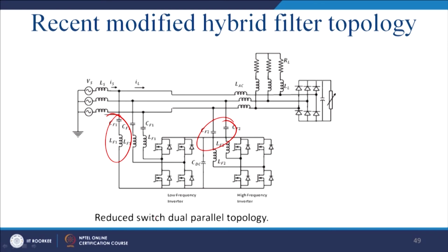Thus, for this reason, we leave everything to the combination. This part will compensate the 5th and 7th, and this part will compensate the 11th and 13th. We have found that the value of LC, LSC required is less compared to Akagi's work. And one leg we have reduced, since it is a 3 phase 3 wire system. One leg is connected to the end point of the DC bus, so that there are no fluctuations of the DC bus. You can connect this leg to the midpoint of the DC bus.